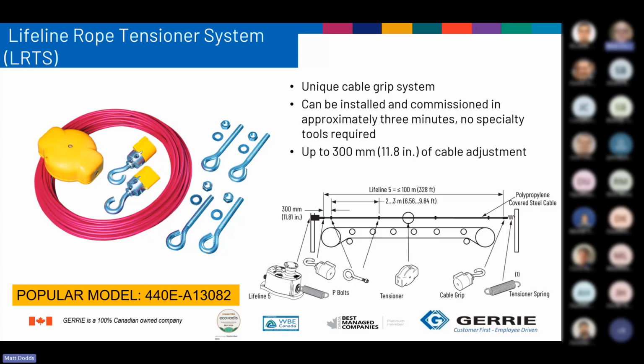The eye bolts are designed to support the cable, because if you had a machine with some vibration, that cable is going to start resonating and bouncing all over the place. It also maintains a uniform pull, so no matter where I pull the rope, it's going to be the exact same distance I pull it for it to actuate. And the cable grips need no tool installation. You simply slide the cable through the grip, and the excess can go in the little holder there. So again, it's a pretty quick and easy installation.